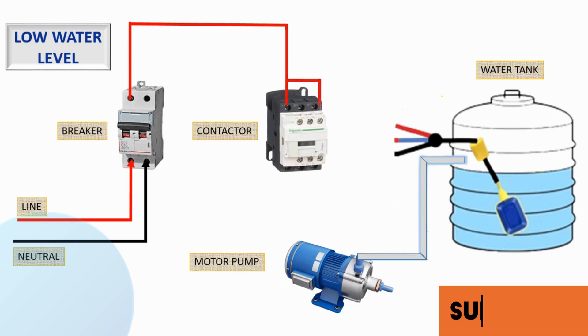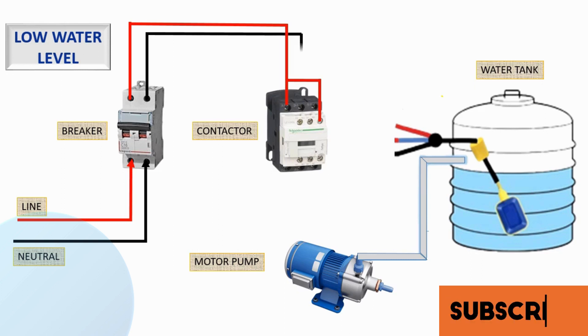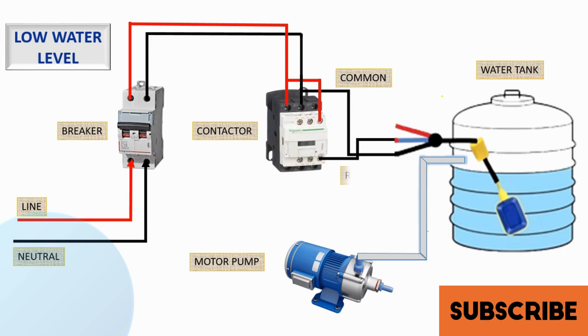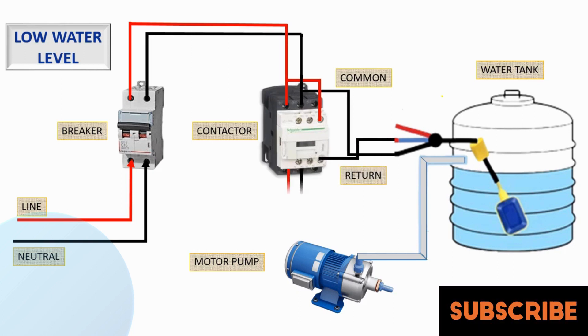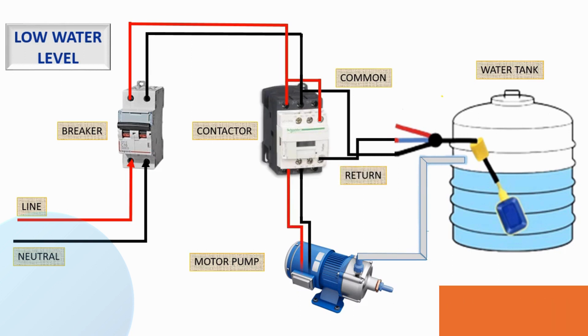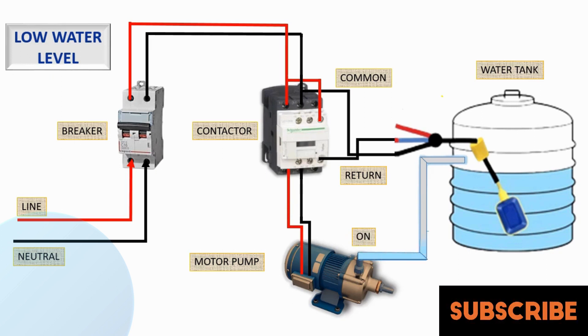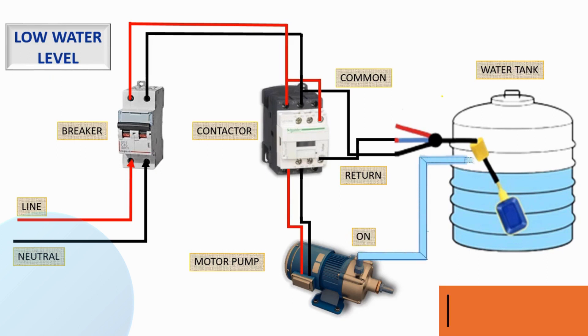Control circuit action: The control circuit monitors the status of the float switch. If the float switch indicates a low water level, it commands the motor to start. As the motor runs, water is drawn into the system, raising the float switch.